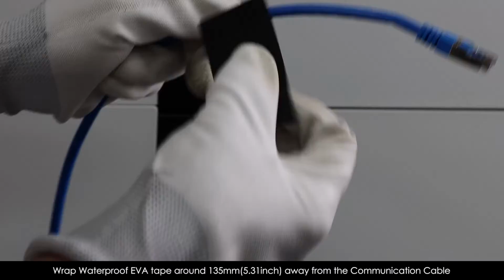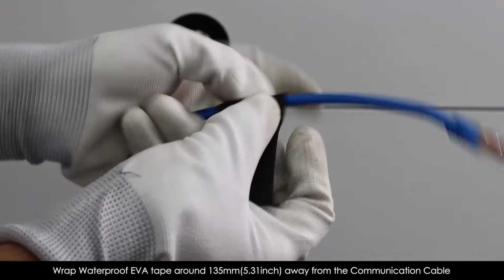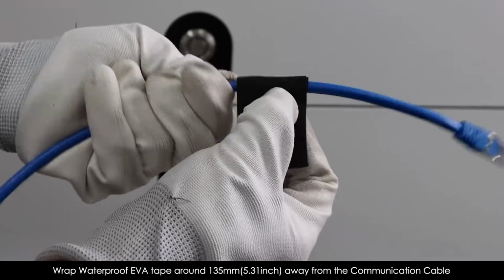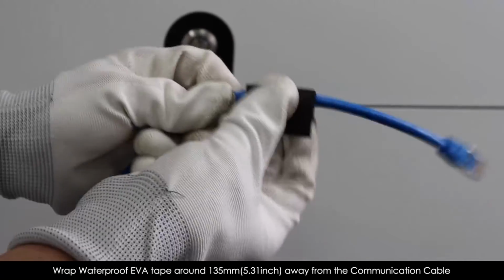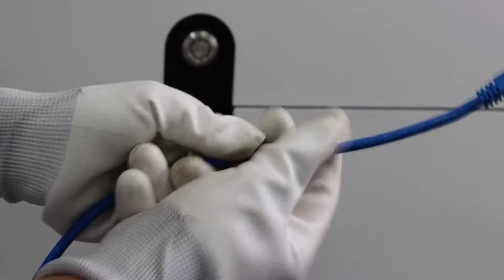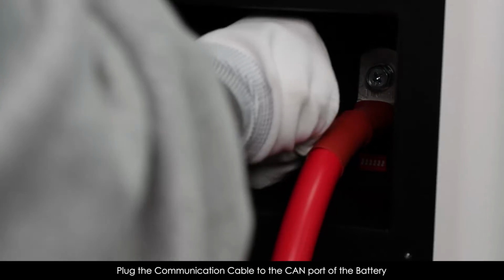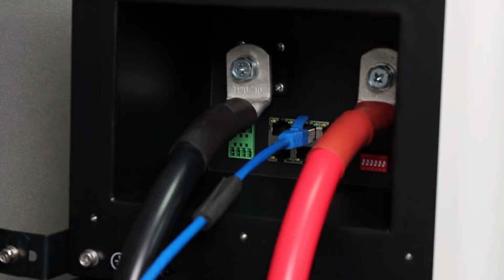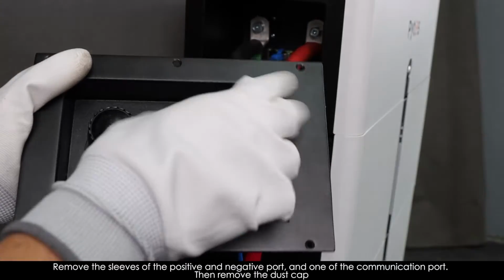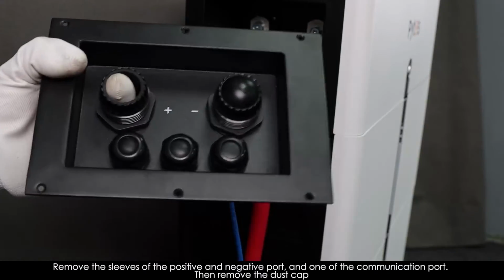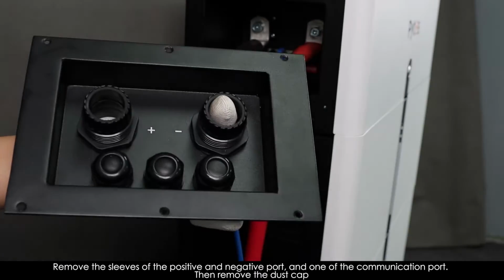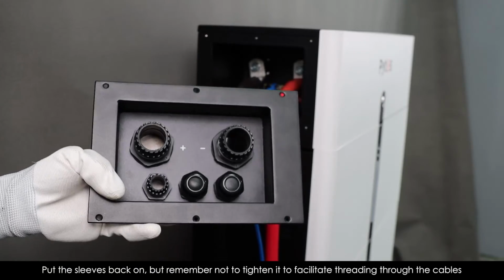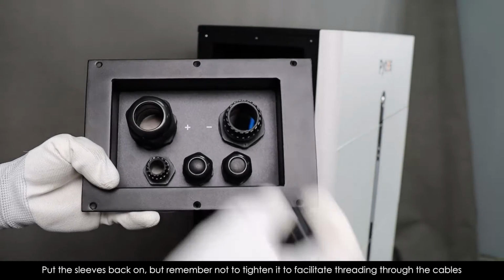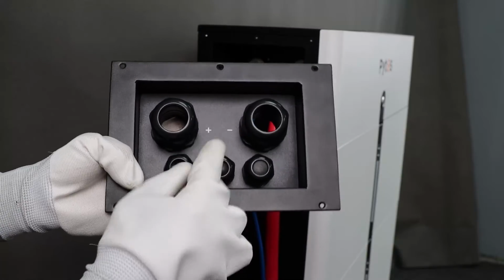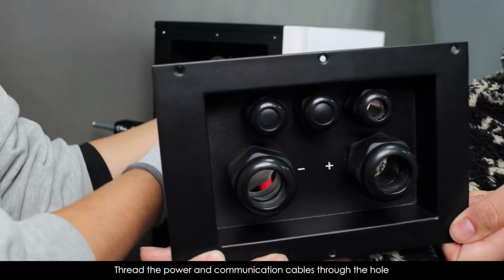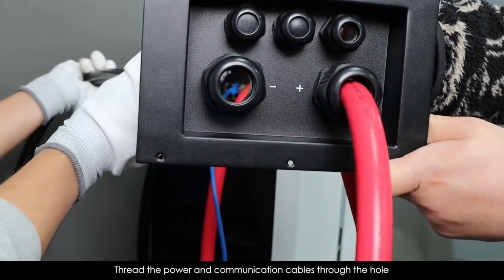Wrap waterproof EVA tape around 135 mm, which is 5.31 inch, away from the communication cable. Plug the communication cable to the CAN port of the battery. Remove the sleeves of the positive and negative port and one of the communication port, then remove the dust cap. Put the sleeves back on, but remember not to tighten it to facilitate threading through the cables. Thread the power and communication cables through the hole.